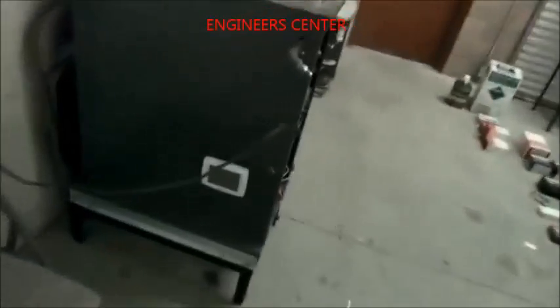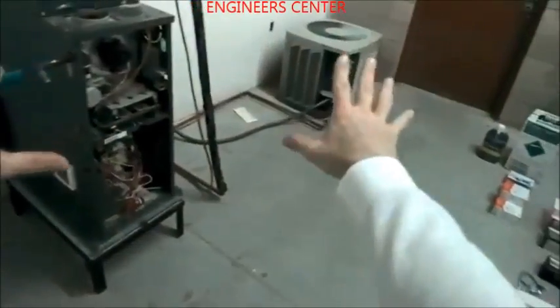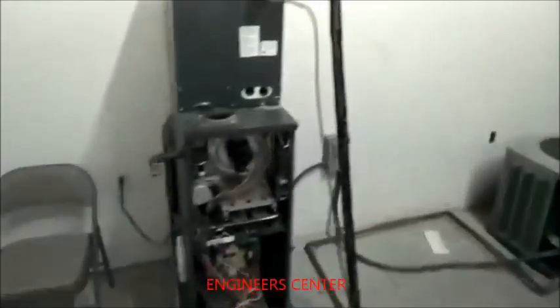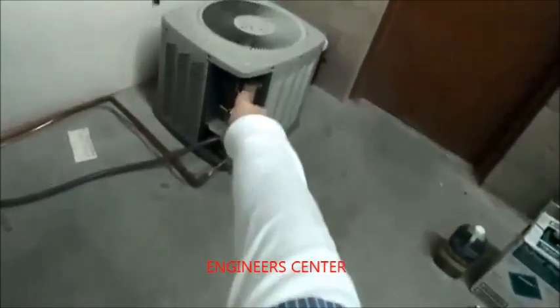Let's go look at an air conditioner here. You've got to know the sequence of operation of something in order to diagnose it. The sequence of operation in this system here, a straight cool unit, condenser, and furnace, is that we'll come to the thermostat here, and we'll turn it on. Cool, auto, and 60 degrees. And so what's going to happen next? Sequence of operation: the blower motor is going to turn on, and this is going to turn on, the compressor and the condenser.